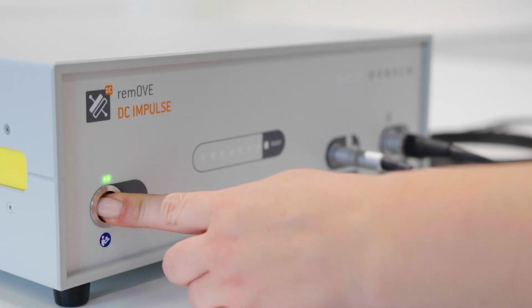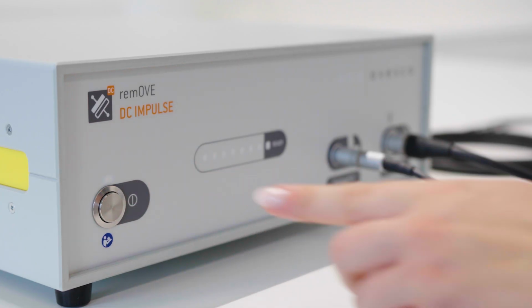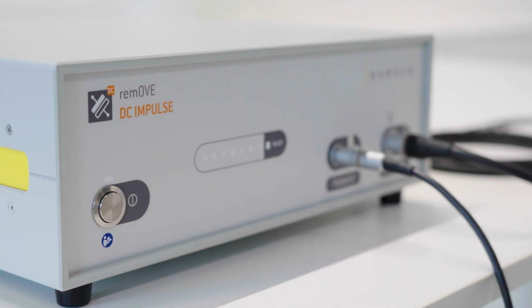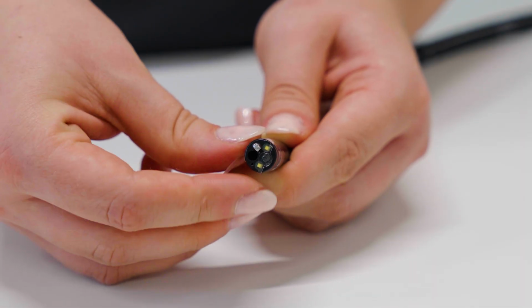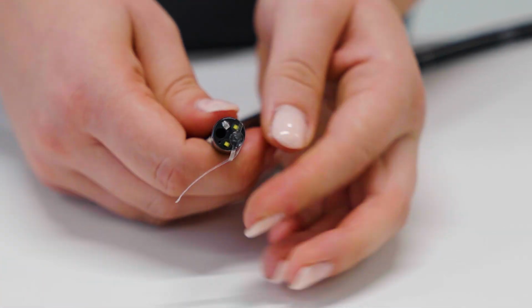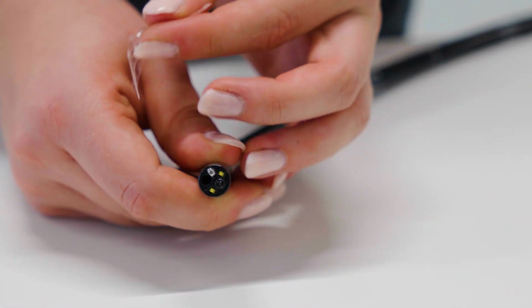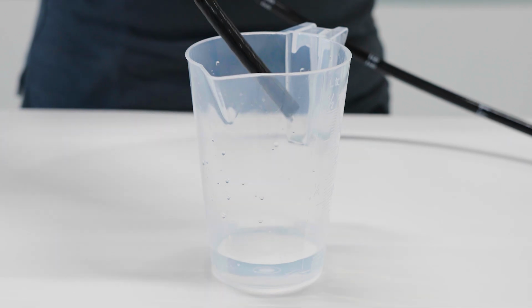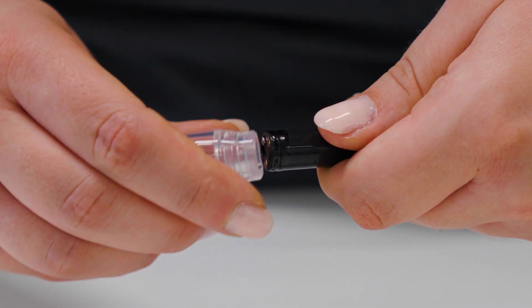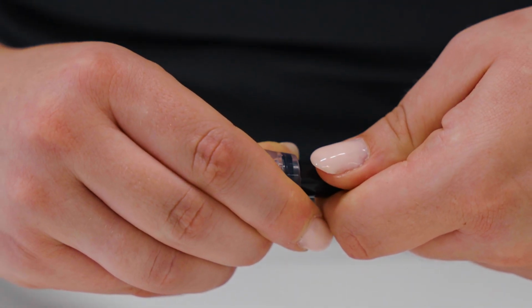After severing the clip, switch off the remOVE DC impulse, then remove the endoscope from the patient. The remOVE shield and the remOVE DC cutter are disposed of after the cutting procedure is complete. To retrieve the clip fragments, first moisten the endoscope tip, and then mount the remOVE secure cap.